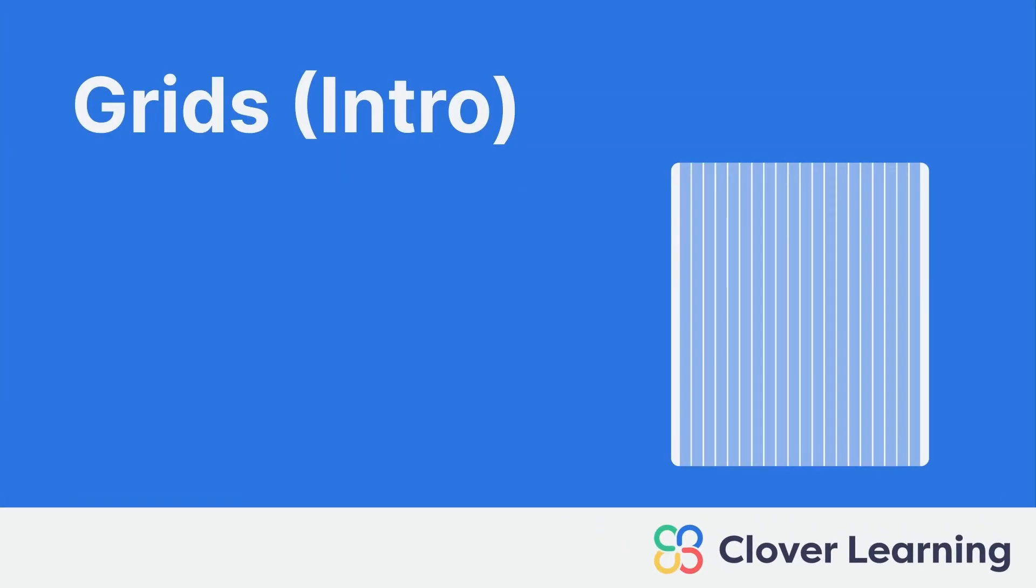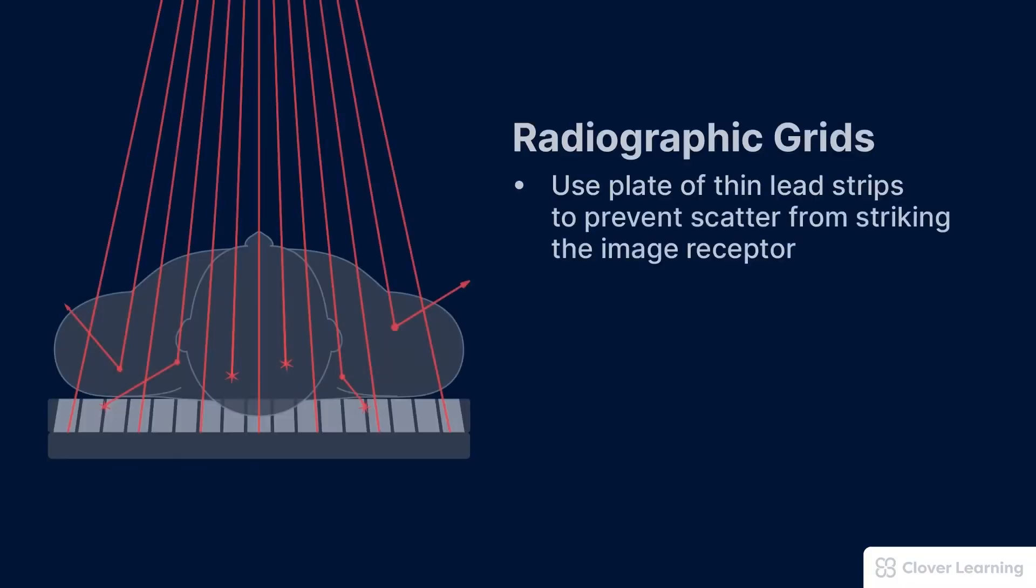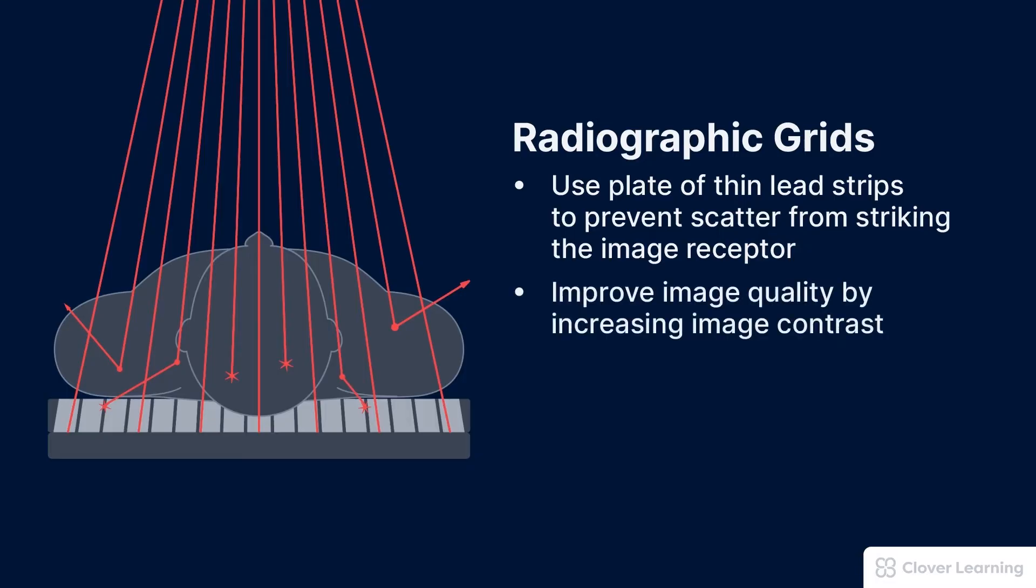Hey everybody, welcome back. In this video we're discussing radiographic grids. Radiographic grids have a very specific design and purpose. A grid uses a plate of thin lead strips to prevent scatter from striking the image receptor and that improves image quality by increasing image contrast.